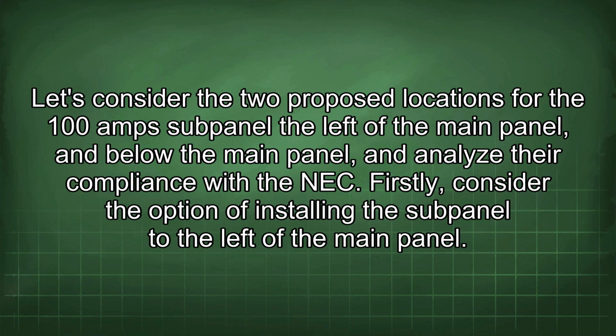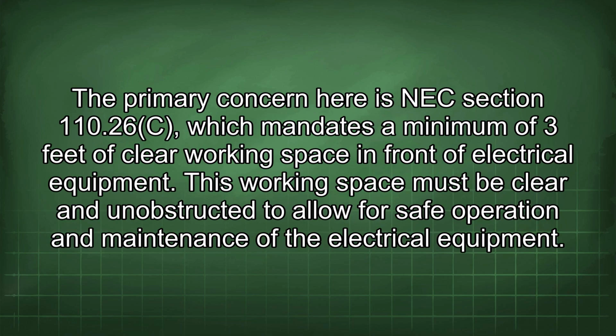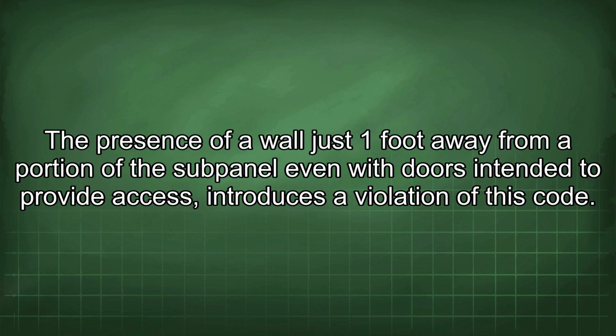Firstly, consider the option of installing the subpanel to the left of the main panel. The primary concern here is NEC Section 110.26(C), which mandates a minimum of 3 feet of clear working space in front of electrical equipment. This working space must be clear and unobstructed to allow for safe operation and maintenance of the electrical equipment. The presence of a wall just 1 foot away from a portion of the subpanel, even with doors intended to provide access, introduces a violation of this code.